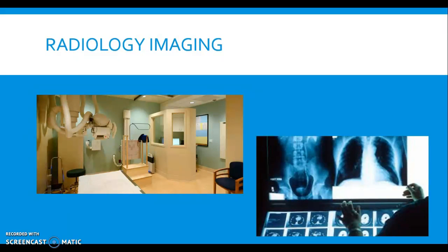The following slide shows what a common radiology room looks like. On the left, you have a tube, you have a console. The console is surrounded in lead, along with the room being surrounded in lead. Radiation is something that is very well monitored by the state and by the governing bodies. So all rooms are surrounded in lead.